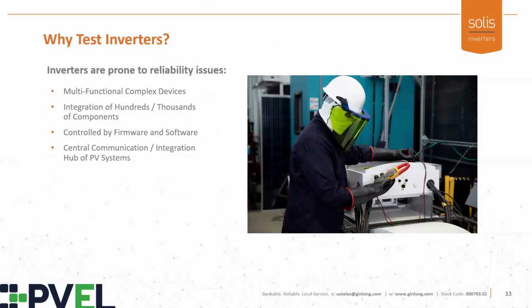So why test inverters? Again, the primary role is to convert this available DC energy to AC output energy, doing this while abiding by the local interconnection rules and monitoring the grid side for safety issues. So that's the interconnection tests that were mentioned by Terence when he talked about 1547. On top of this, with these newer mandates for command and control, they have to provide data up in terms of how they're operating, as well as accept data commands down to go to different set points. Non-unity power factor comes to mind as an application.